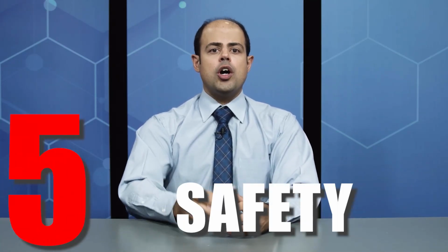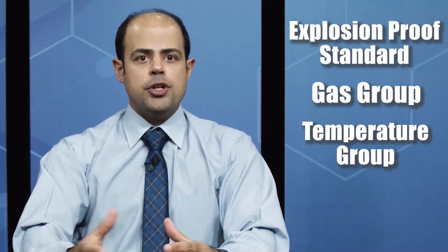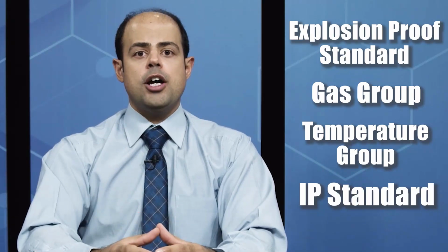In the fifth step, we're dealing with one of the most vital items. For sure, safety requirements are the main prerequisite to start any industrial job. In this section, there are many obligations and rules which we need to bear in our mind. Explosion-proof standard, gas group, temperature group, and IP standard must be applied to design a field instrument. For instance, in operational zone 0, we must apply an instrument certified with intrinsically safe explosion-proof type, Ex i, based on IEC 60079 Section 11 standard.